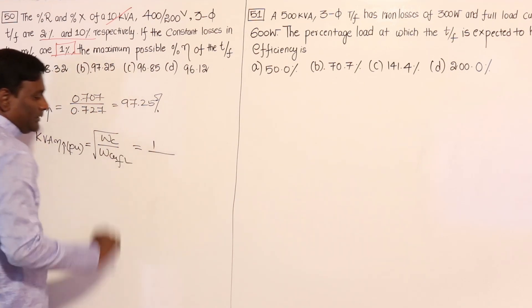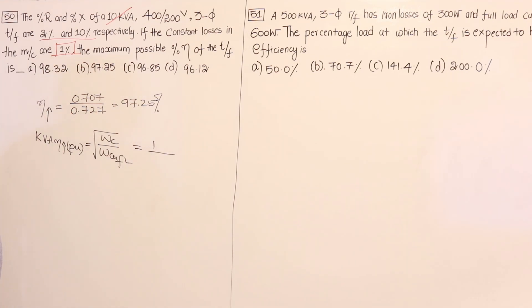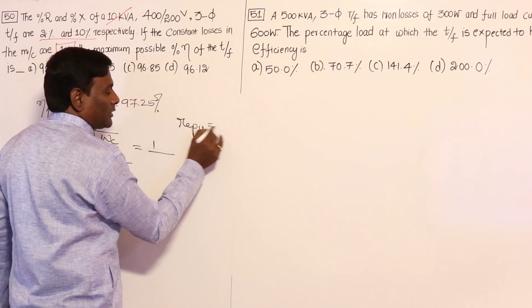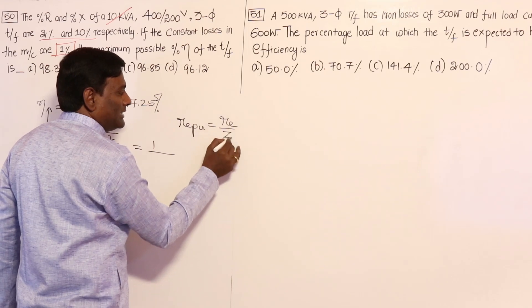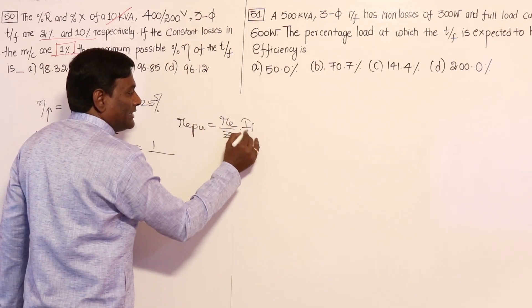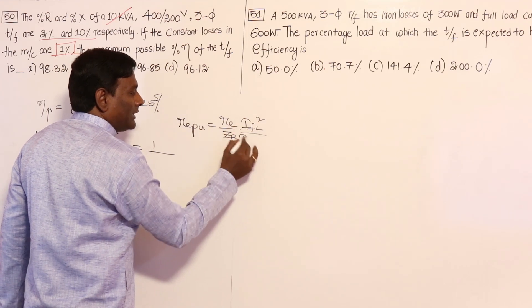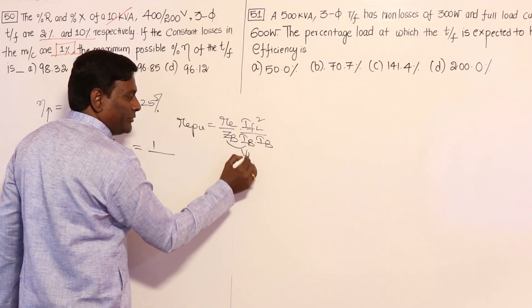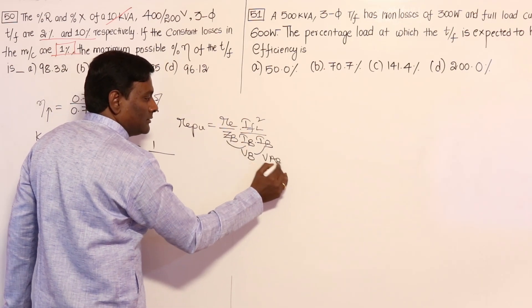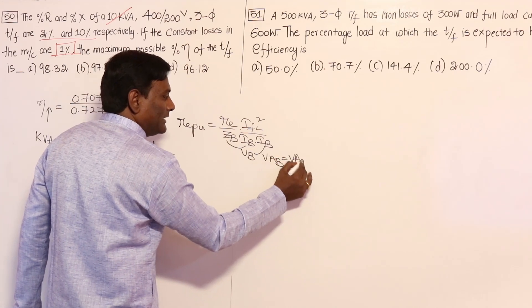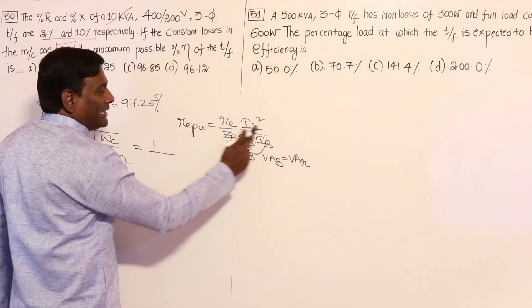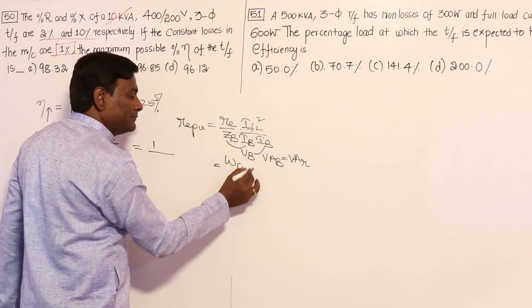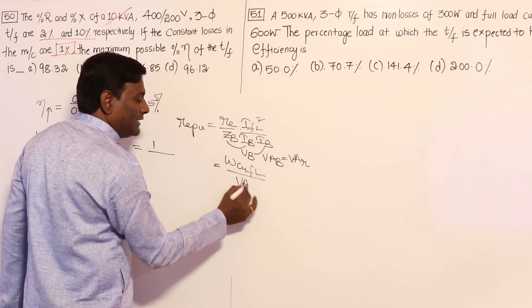The full load copper loss is nothing but RE per unit. RE per unit equals RE divided by Z-base, times I_FL squared divided by I-base squared. Z-base times I-base equals V-base, and V-base times I-base equals VA-base, which is VA rated for a transformer. So I_FL squared times RE equals full load copper loss, and dividing by VA rated gives copper loss full load per unit.